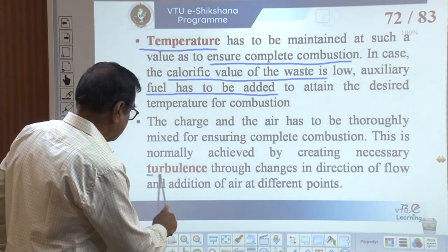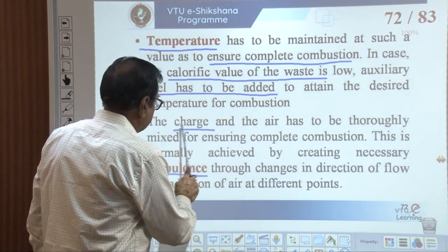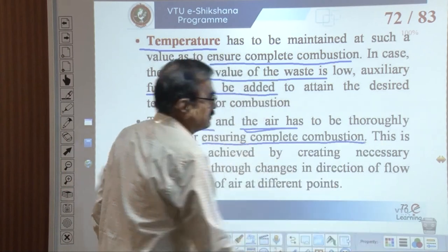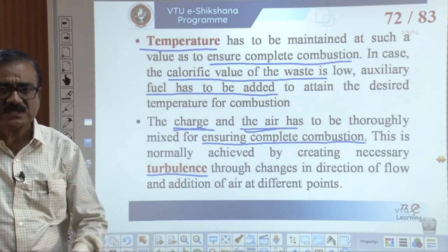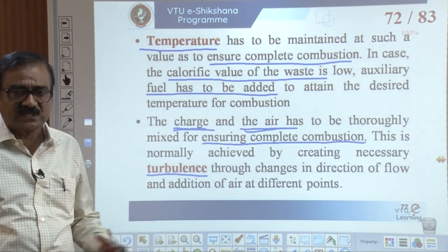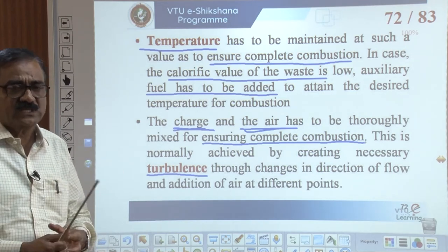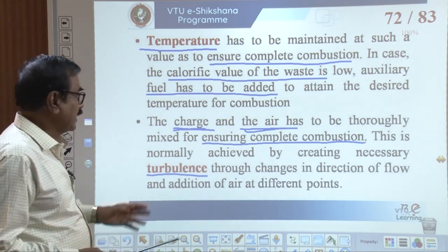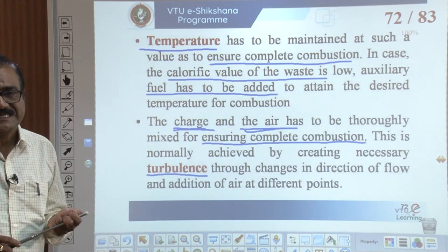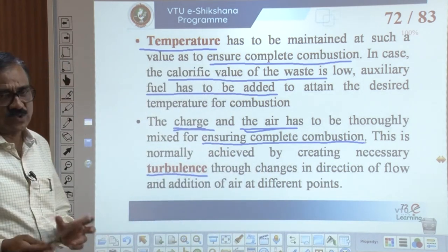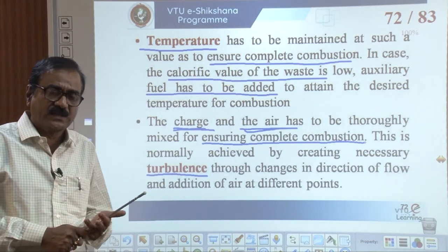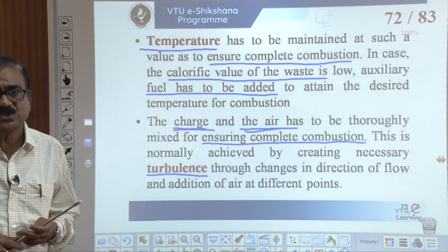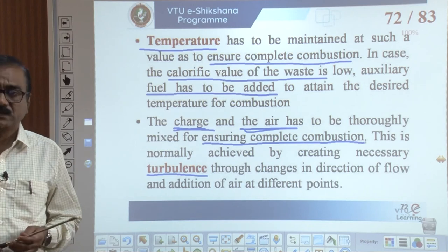The last T is turbulence. The charge — solid waste — and the air supply must be thoroughly mixed to ensure complete combustion. Air is coming from the bottom and a batch charge of solid waste is coming in; the arrangement should be such that there is proper mixing. Proper mixing, sufficient time, and a minimum of 900 degrees Celsius temperature — if all three are there, we can expect efficient working of the incinerator. This norm is achieved by creating necessary turbulence. Even if temperature and time are sufficient, improper mixing still means complete combustion of the combustible material cannot be ensured.